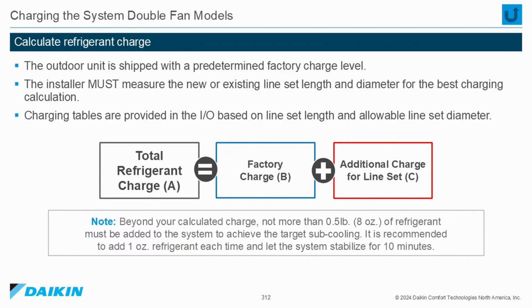Note, beyond your calculated charge, not more than 0.5 pounds or 8 ounces of refrigerant should be added to the system to achieve the target subcooling. It is recommended that you add 1 ounce of refrigerant each time and let the system stabilize for 10 minutes.